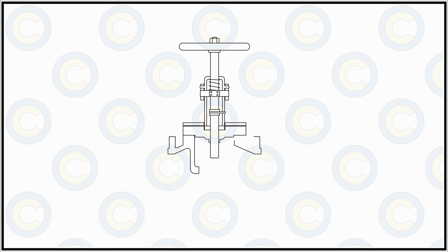So now let us, for example, say the outlet valve of a cylinder oil tank or a lube oil tank. Basically all those tanks which have bulk quantity of fuel and lubes that are flammable in nature, and also the waste oil tanks, because again that is also a highly combustible mixture which is present in the tank. So we would want these tanks to be automatically isolated on their outlet lines, that is the inlet to the main system. So what we end up doing is that we end up installing quick closing valves on these lines.